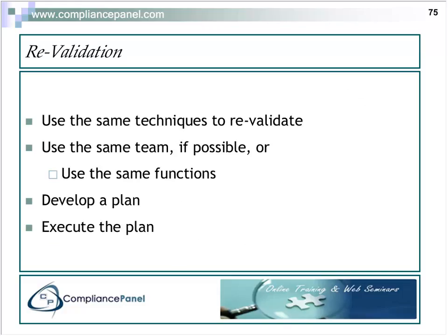We need to use the same techniques if we have to revalidate. We need to use the same team if they're still around, or use the same functions to do the revalidation. And before we do a revalidation, we need to have a plan and we need to execute the plan. We need to have a protocol to follow. We may be able to use the same protocol, but a new report with the results from this change.